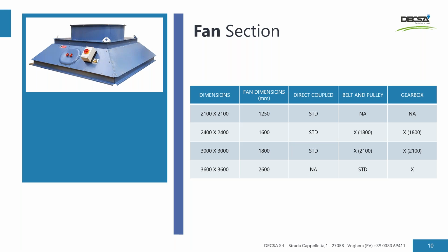But in this case, we have 2 more options. In fact, the unit can be made with the motor coupled to the fan by a V-belt transmission or by a gearbox. On the bigger cell, the 3600 by 3600, we have, as a standard, the V-belt transmission and, in alternative, the gearbox transmission. In this table, you can see that when we change from direct coupled to V-belt or gearbox transmission, we also increase the dimensions of the fan. This is a must because we also change the motor from 8 poles of the direct coupled version to the 4 poles of the V-belt or gearbox transmission.